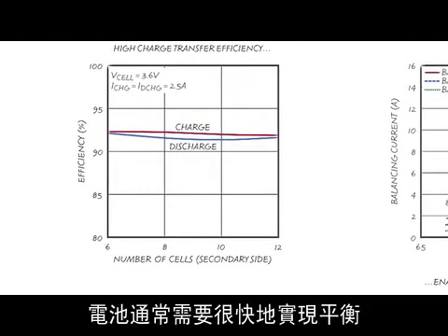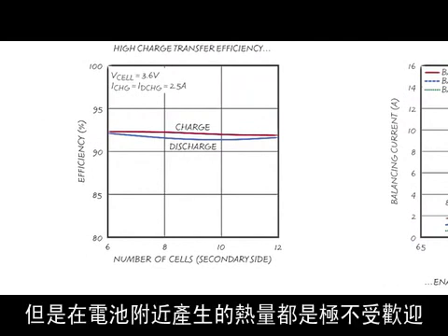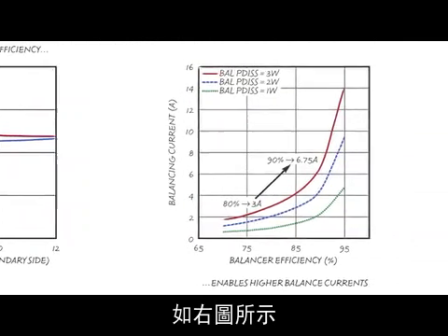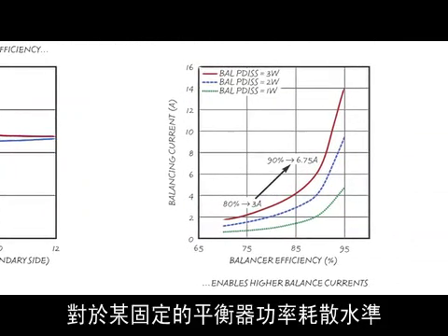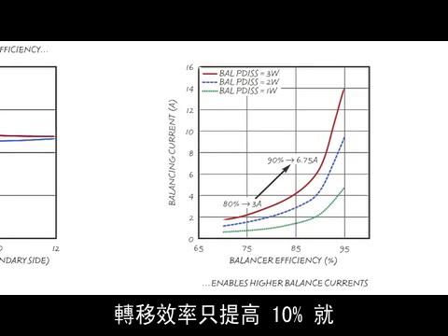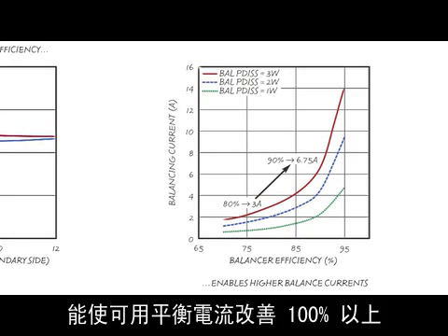Batteries often need to be balanced quickly, but any heat generated near the batteries is highly undesirable. As shown in the graph to the right, a mere 10% improvement in transfer efficiency can result in over 100% improvement in available balance current for a fixed level of balancer power dissipation.